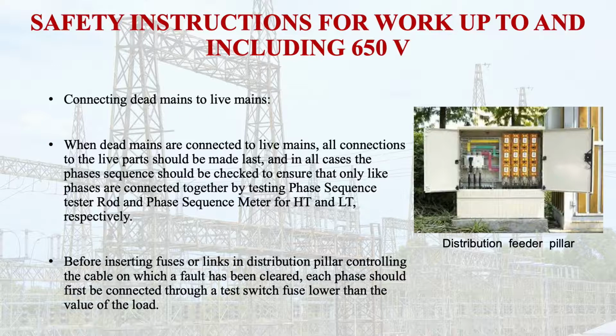Then, before inserting fuses or links in a distribution pillar controlling the cable on which the fault has been cleared, each phase should first be connected through the test switch fuse lower than the value of the load. So you should remember this. First of all, we are using the testing fuse here, which is lower than the value of the load.